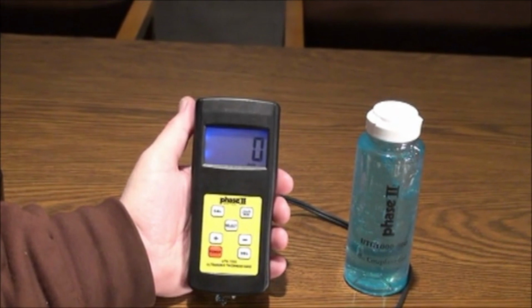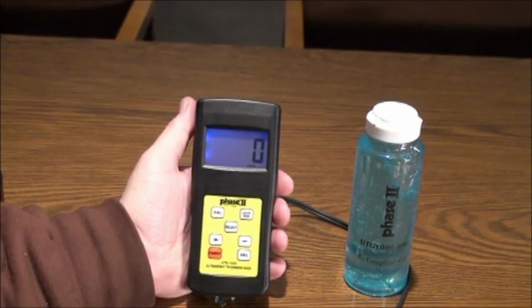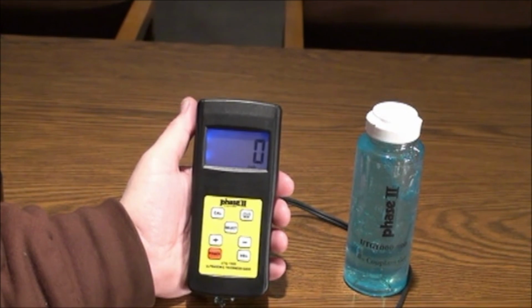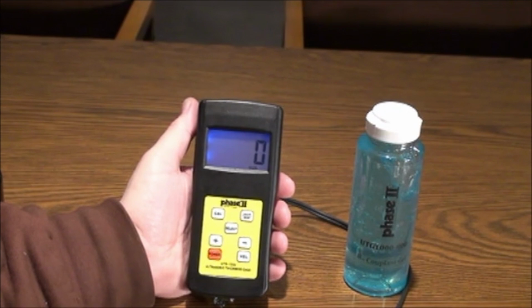The technology incorporated utilizes a simple ultrasonic dual-element transducer that transmits and receives sound waves. Generally, velocity of sound through the material to be tested is a known value and usually supplied via chart in the manual. In case of the UTG-1500, we have preset some general material velocities for your convenience. You always have the option to manually preset the velocity of any material.